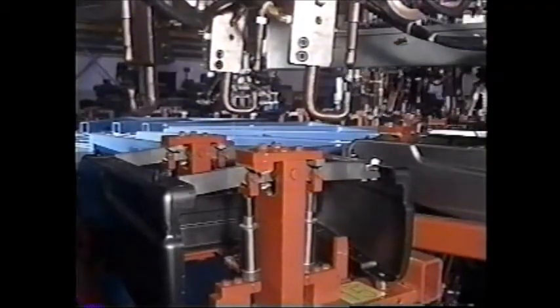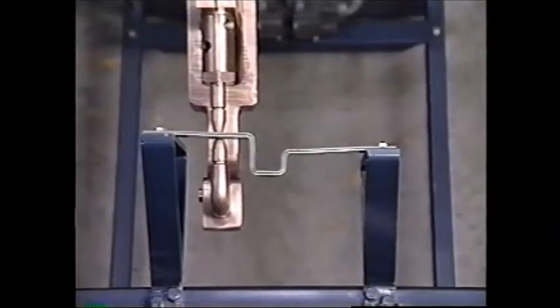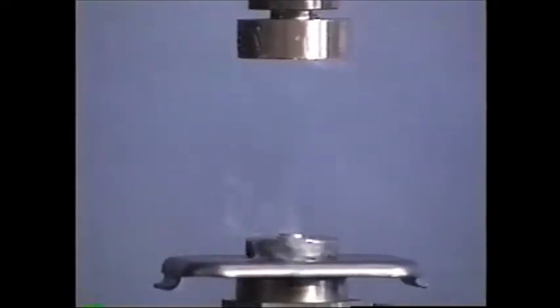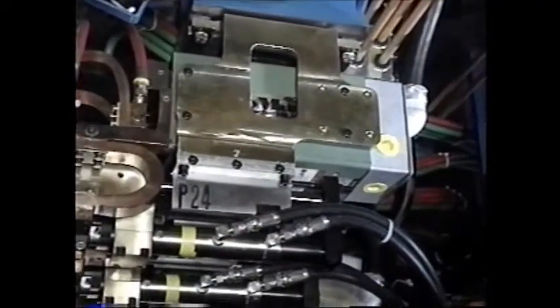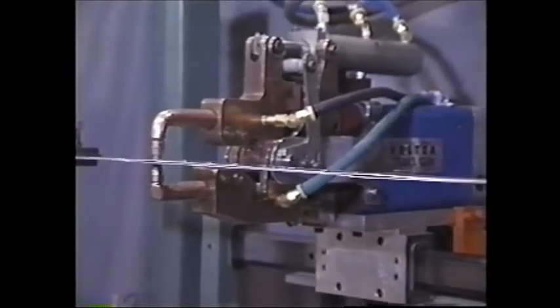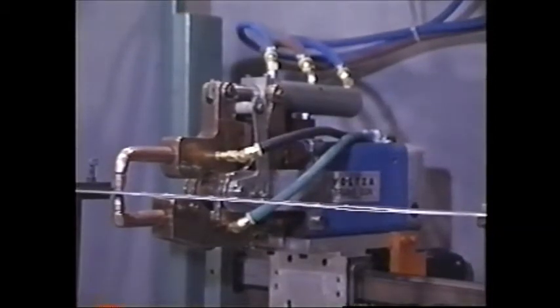The latest innovation and fastest growth area in resistance welding transformers is the transgun type transformer. The transgun, as the name implies, was designed as an integrated combination of transformer and welding gun, resulting in very short secondary conductors which greatly reduce electrical losses in the welding circuit. This is in comparison to the conventional arrangement of separate transformer, secondary conductors, and weld gun. In this unique application, the size, weight, and interchangeability of the transformer are the most critical factors. To minimize size and weight, the transgun transformer provides only one secondary voltage and employs a highly refined and optimized transformer design.